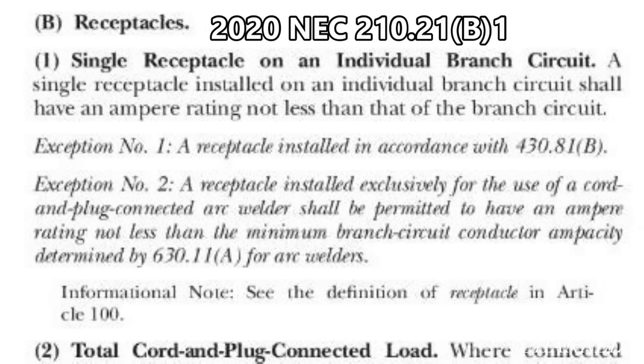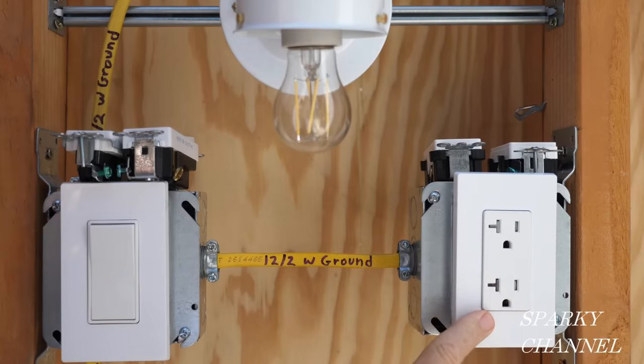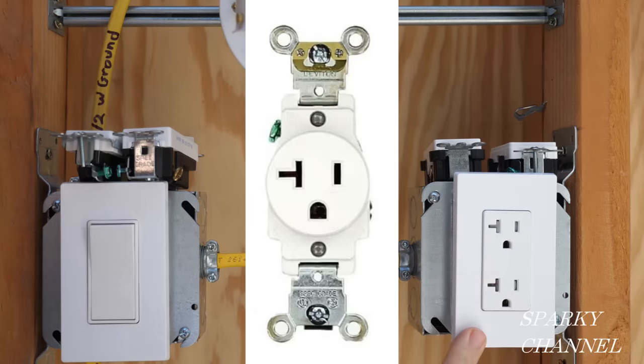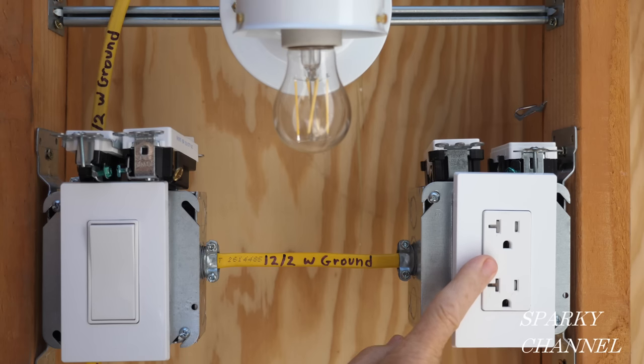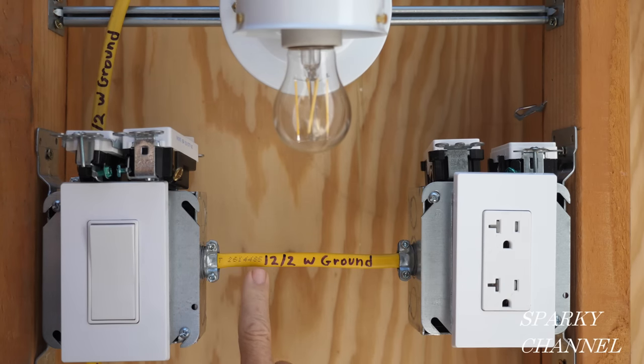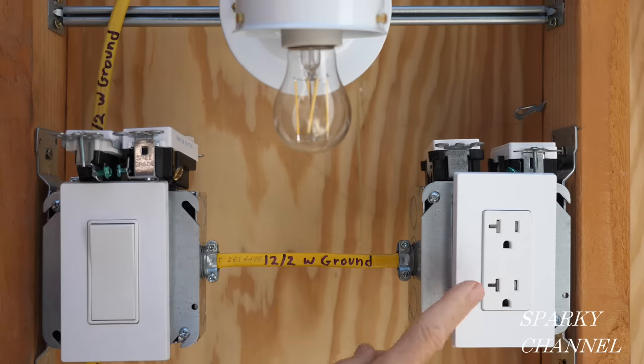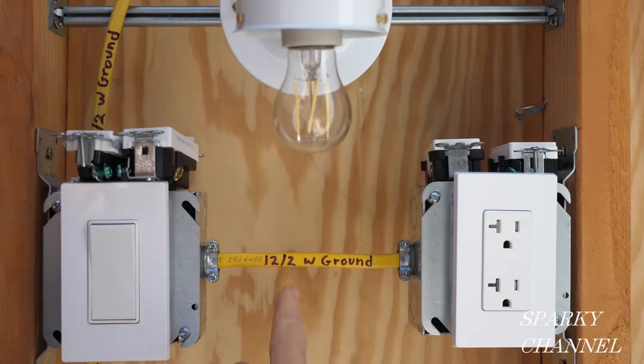NEC 2020 section 210.21B1 covers a single receptacle on an individual branch circuit. This is a duplex receptacle — a single receptacle has just one outlet. A single receptacle installed on an individual branch circuit shall have an ampere rating not less than that of the branch circuit. So if I put a single receptacle on a 20 amp circuit with 12-2 with ground, I have to use a 20 amp single receptacle.